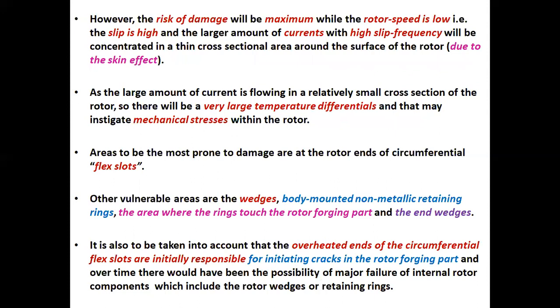The risk of damage will be maximum while the rotor speed is low, that is the slip is high, and the large amount of currents with high slip frequency will be concentrated in a thin cross-sectional area around the surface of the rotor due to the skin effect. As the large amount of current is flowing in a relatively small cross-sectional area around the rotor, there will be very large temperature differentials that may instigate mechanical stresses within the rotor.